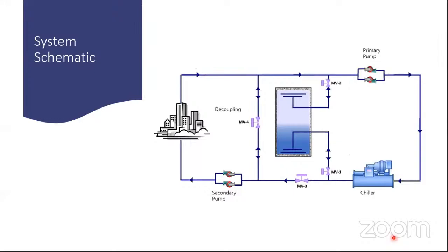Just to quickly understand the schematic, how the flow works in a thermal storage system where the objective is demand management. There is a chiller with a primary pump, and this configuration is primary constant, secondary variable. This is the stratified chilled water tank here, and these are secondary pumps, and this is our building load. This is the general schematic, and we will also try to understand these schematics for various modes of operation. In here I will explain that there are generally four modes of operation.